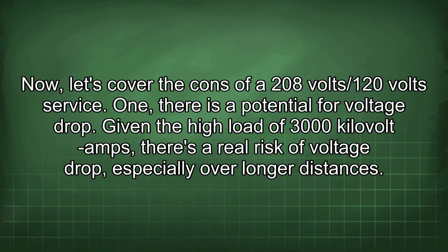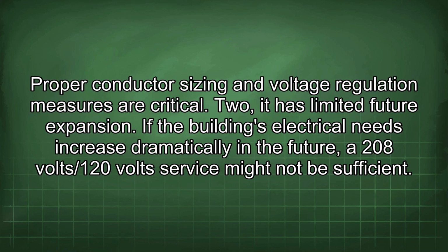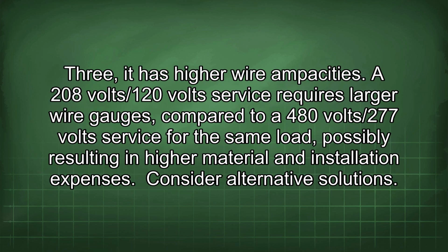1. There is a potential for voltage drop. Given the high load of 3,000 kilovolt amps, there's a real risk of voltage drop, especially over longer distances. Proper conductor sizing and voltage regulation measures are critical. 2. It has limited future expansion. If the building's electrical needs increase dramatically in the future, a 208 volts/120 volt service might not be sufficient. 3. It has higher wire ampacities. A 208 volts/120 volt service requires larger wire gauges compared to a 480 volts/277 volt service for the same load, possibly resulting in higher material and installation expenses.